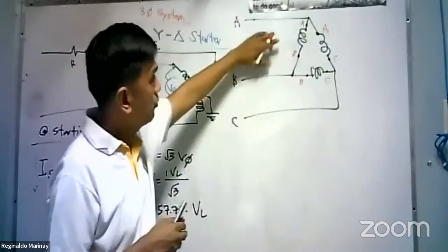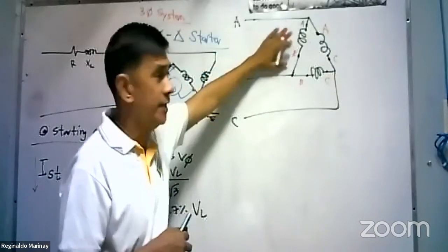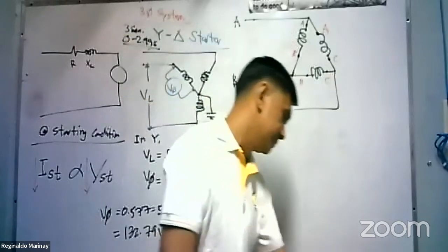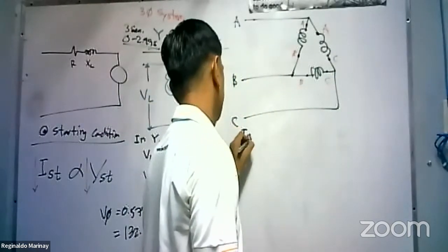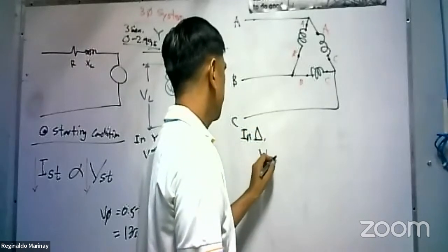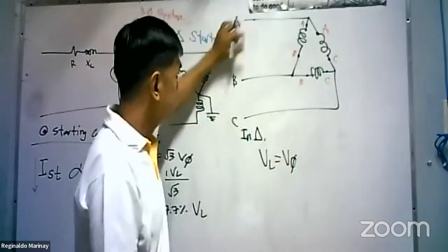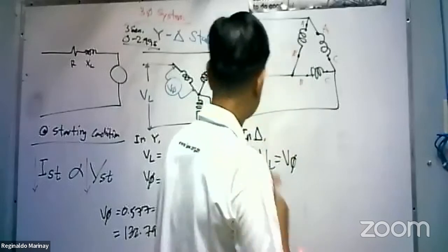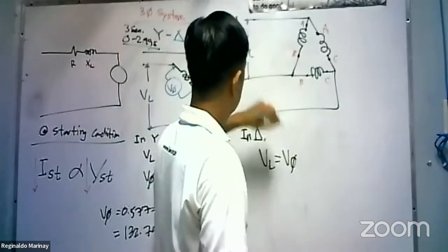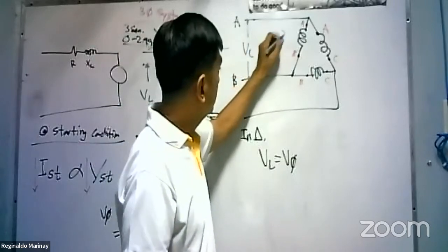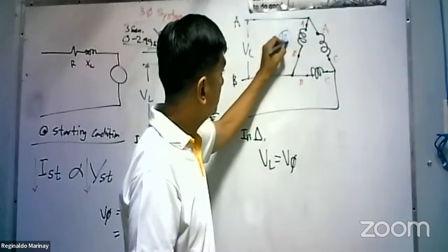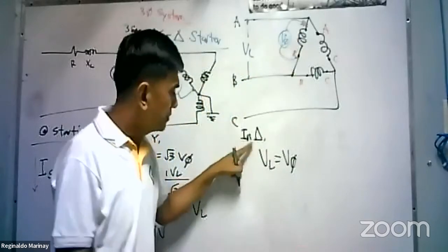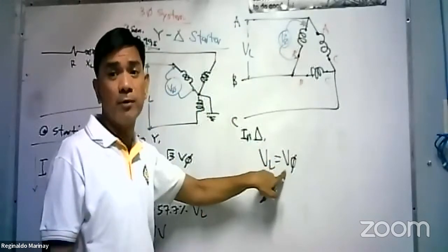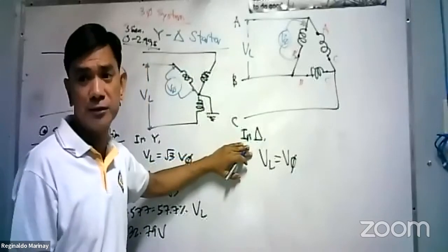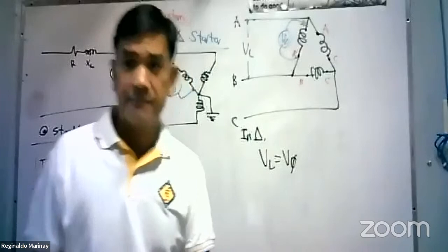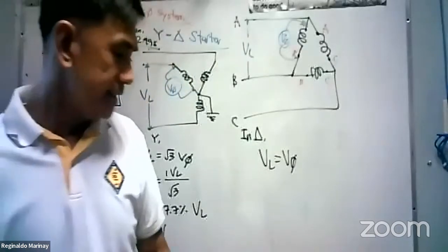Once you reach 3 seconds, the winding of the motor becomes delta. So therefore, in delta connection, take note of this. In delta, our line voltage is simply equal to the phase voltage. If that is 230 volts, this will also be equal to 230 volts, the phase voltage, because the basic idea of delta is the line voltage is equal to the phase voltage. In delta connection, always remember that. Okay? Let's take a look at our circuit.